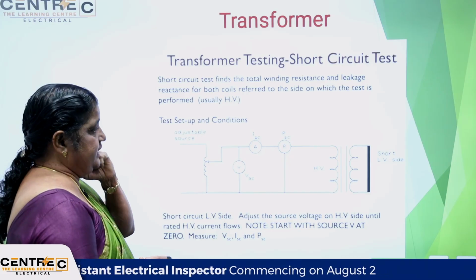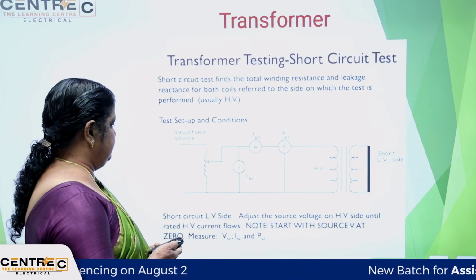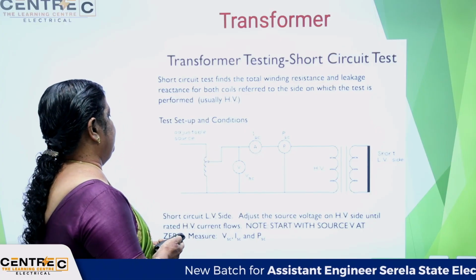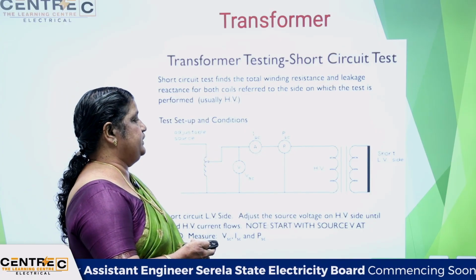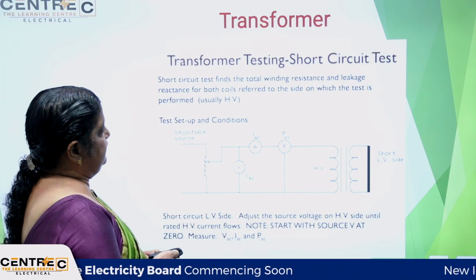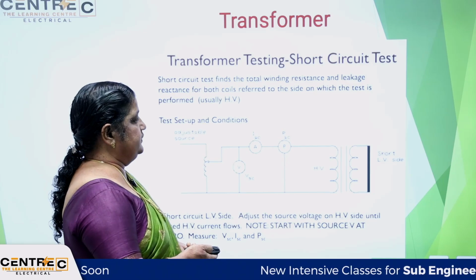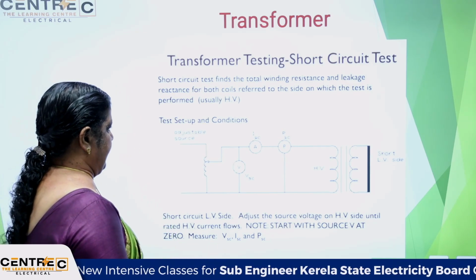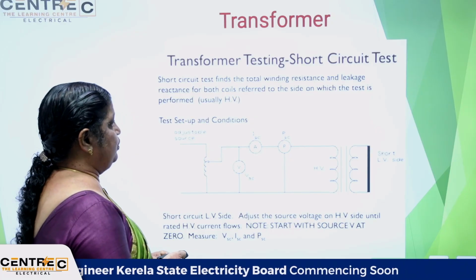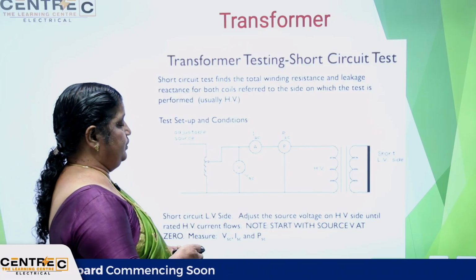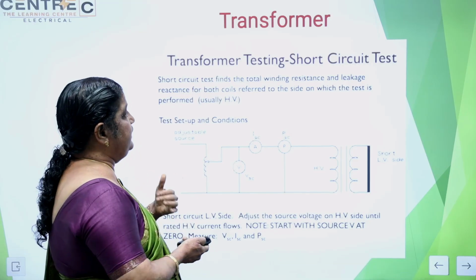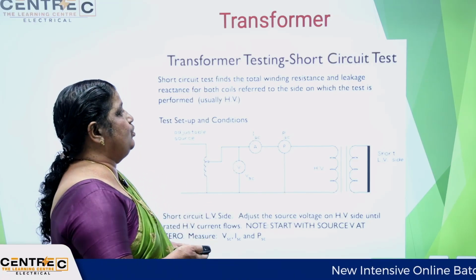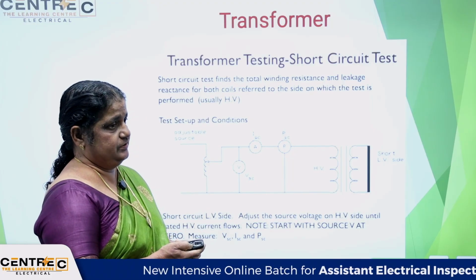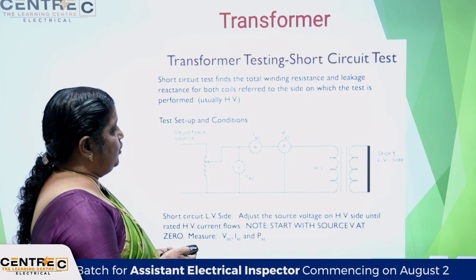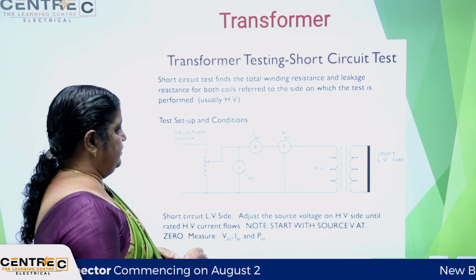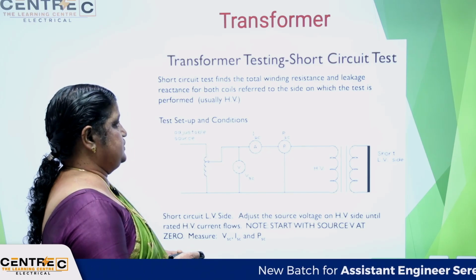Then for the short circuit test, the secondary is shorted and the primary is connected through an auto transformer. The auto transformer is adjusted so that rated current passes through the primary of the transformer. From that we get a voltage and power, which is the copper loss. From the copper loss and core loss found from the short circuit and open circuit tests, we can predetermine the efficiency at different load conditions. The core loss is constant throughout the loading condition, from no load to full load, but the copper loss varies. So from that we can determine the efficiency and other performance of the transformer using these tests.